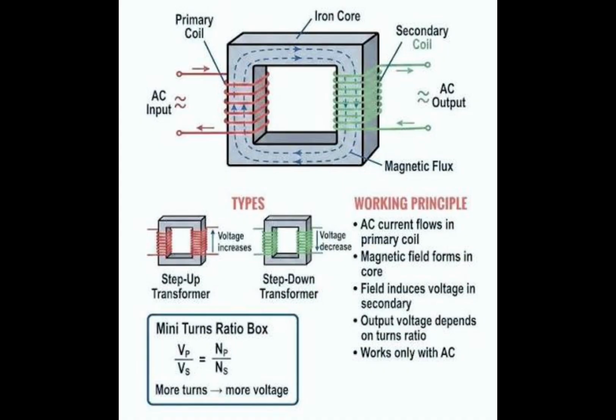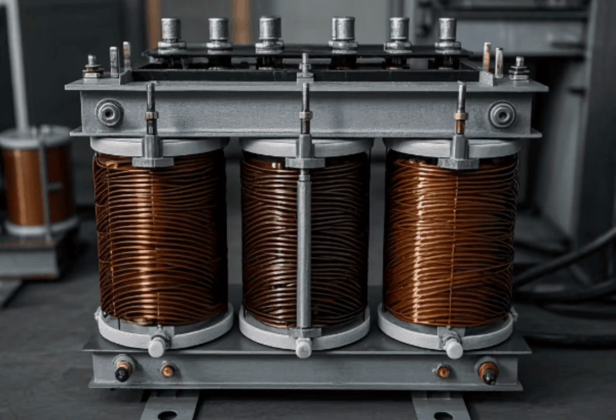This is the primary job of the substation, and it is handled by the most critical piece of hardware on the grid, the Large Power Transformer, or LPT. An LPT is not a solid block of metal. It is an intricate, multi-million-dollar feat of electromagnetic engineering. Inside, massive primary coils of copper wire receive the incoming high voltage. Through the principle of electromagnetic induction, this creates a fluctuating magnetic field in the steel core, which induces a lower voltage in the secondary coils.